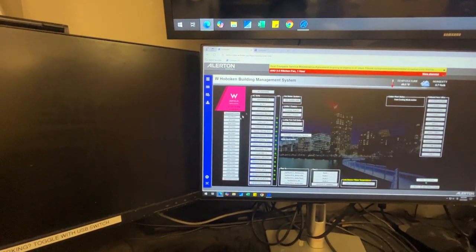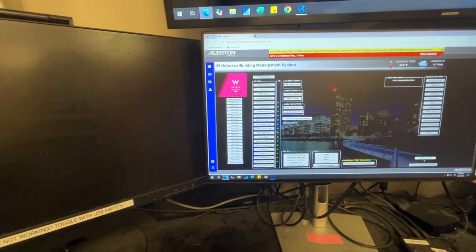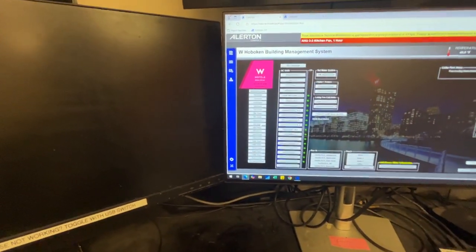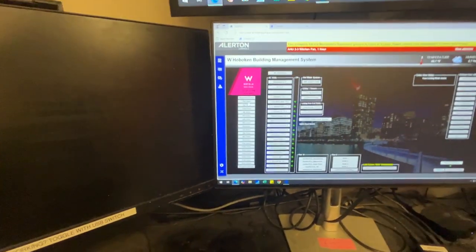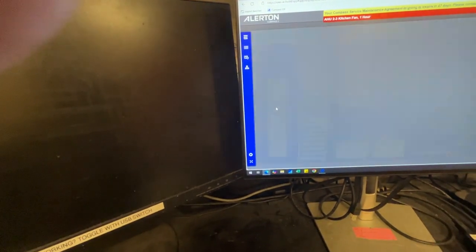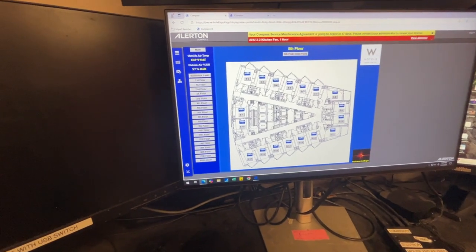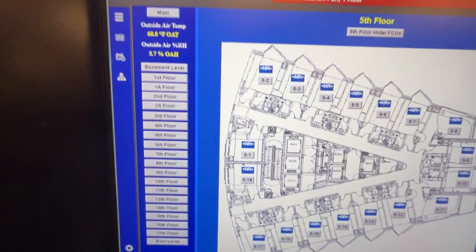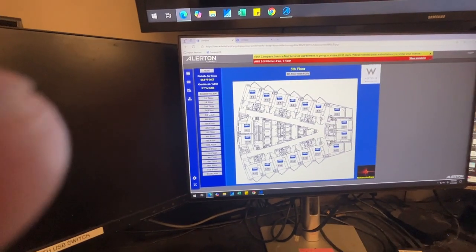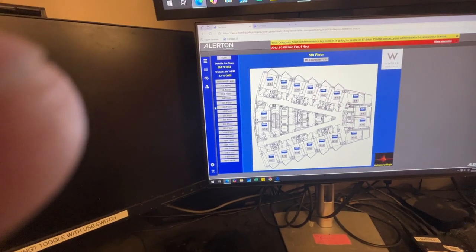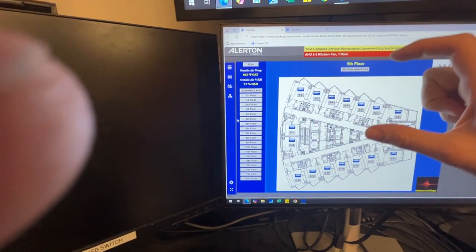top display. So just from the top, these are all being disabled. These need to be disabled. A project was done this year. We installed Incom. It is March 22nd, 2025. Within the last month, we finished this project. So all of these, like fifth floor, this was all Alerton thermostats in the guest rooms. These are removed, and now they just read as NR. So Alerton, one of the projects, Alerton needs to go through and just remove everything third floor through 17 from here. And then Incom will be the new system.